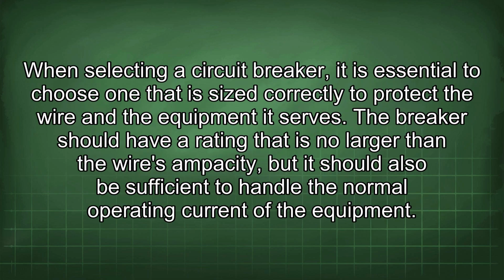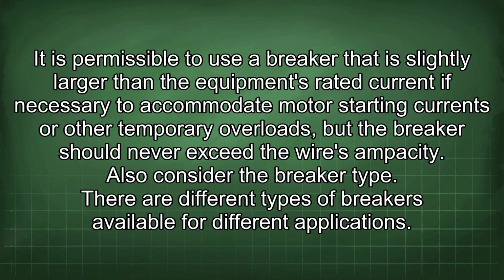When selecting a circuit breaker, it is essential to choose one that is sized correctly to protect the wire and the equipment it serves. The breaker should have a rating that is no larger than the wire's ampacity, but it should also be sufficient to handle the normal operating current of the equipment. It is permissible to use a breaker that is slightly larger than the equipment's rated current if necessary to accommodate motor starting currents or other temporary overloads, but the breaker should never exceed the wire's ampacity.